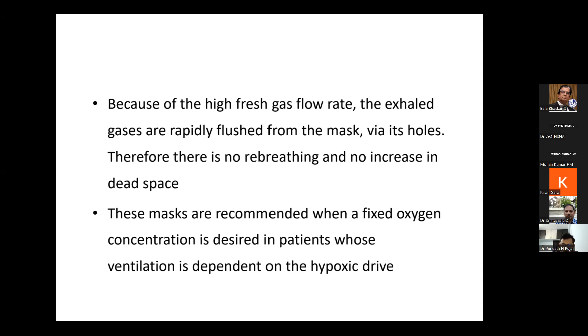Based on the color coding, we see how much air is being entrained and how much total flow is delivered to the patient. Coming to the blue color, it delivers an FiO2 of 24%. The amount of air being entrained is 51 liters per minute, and the total flow to the patient is 53 liters per minute. Compare that with the highest, the green Venturi device. Here the FiO2 is 60%. The amount of air entrained is 15 liters per minute. Compared with the blue one, where the air entrained is 51, in the green it is 15.